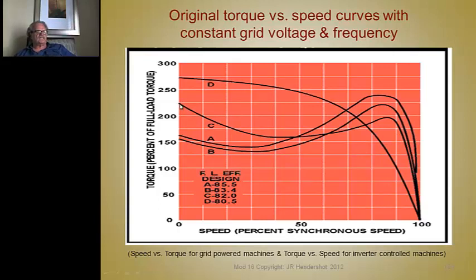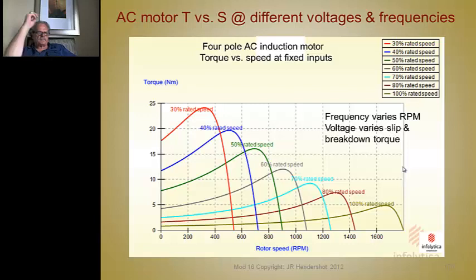So during starting, the current flows in the outer part of the bar, giving you this high starting torque. But once you get up to speed, the current flows in both sections of the bar, so the slope is steep, the slip is lower, and it runs at higher efficiency. But you wouldn't want to use that rotor for an inverter. A properly designed 4-pole induction motor has a type A bar or a NEMA B type bar shape, teardrop shape, close to the OD of the rotor, and lots of bars. Those are the tricks: lots of bars close to the OD and teardrop shape. It can be parallel-sided bars, rectangular bars, but teardrop or rectangular bars.